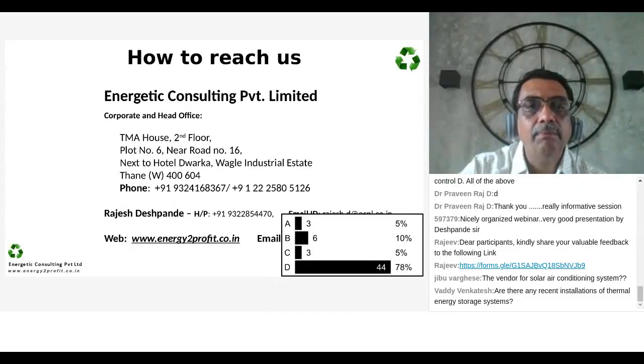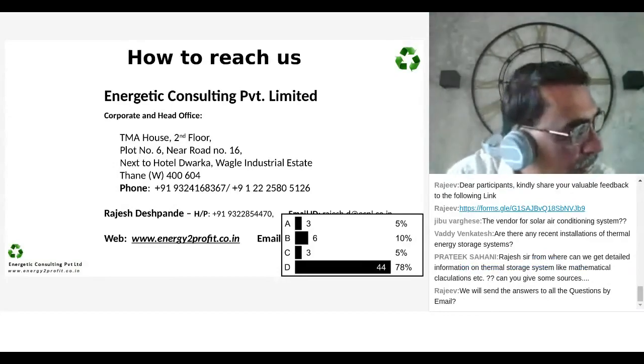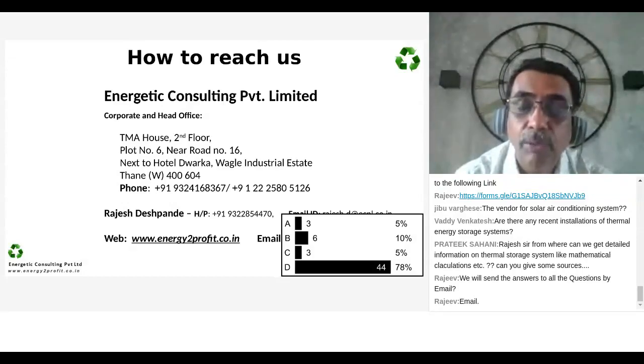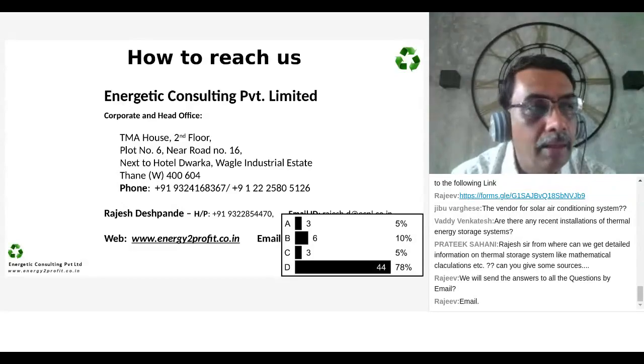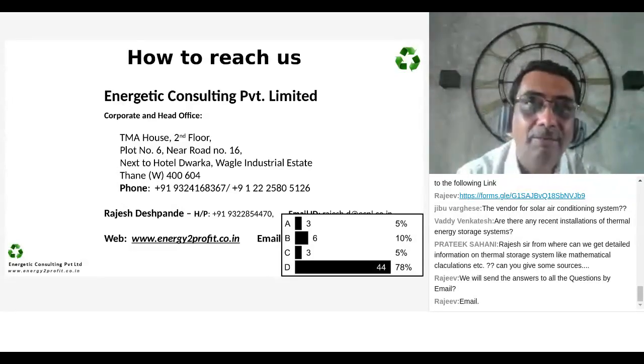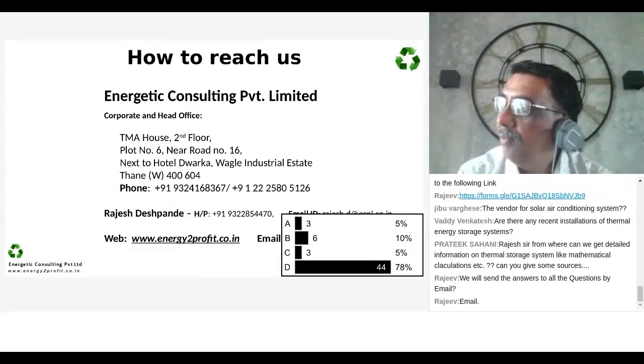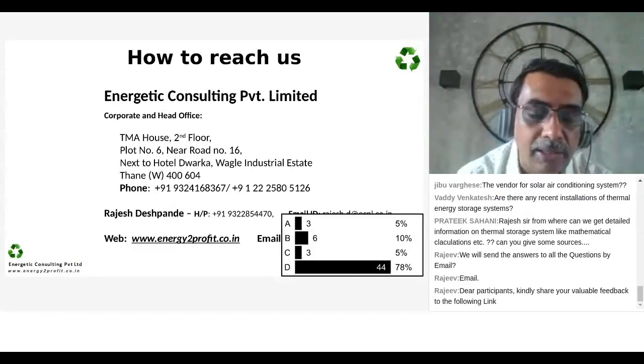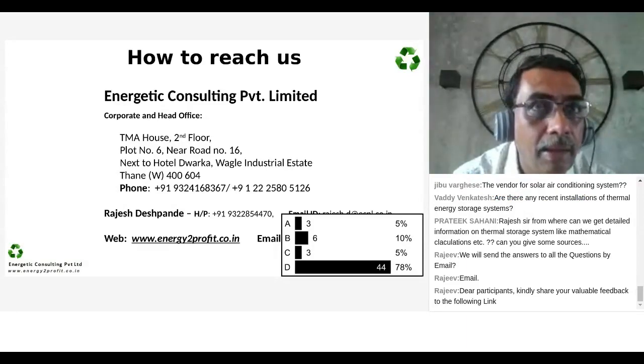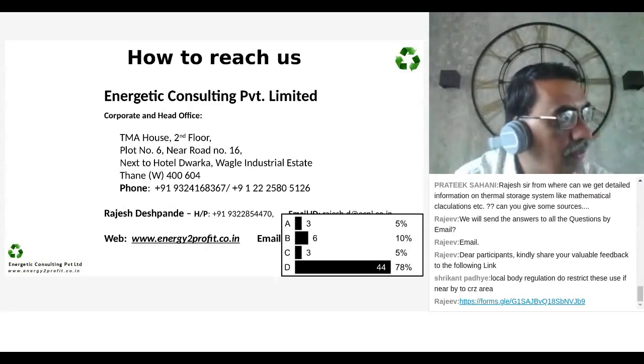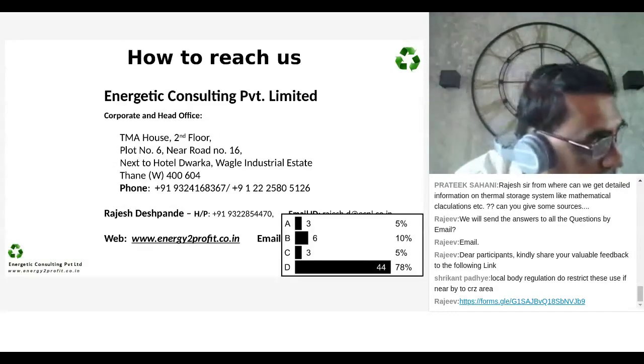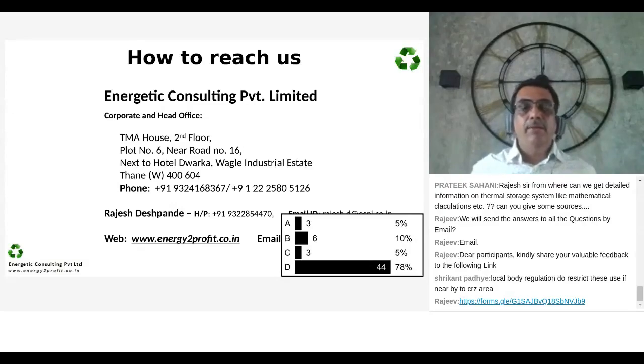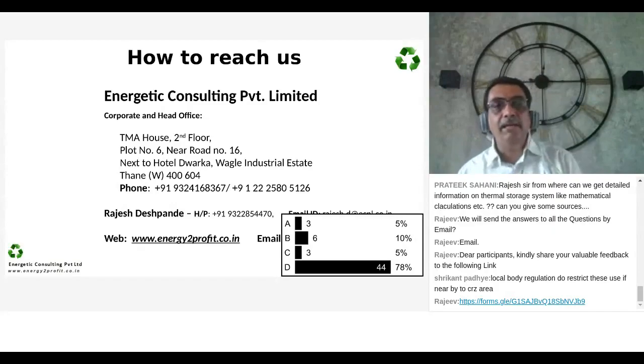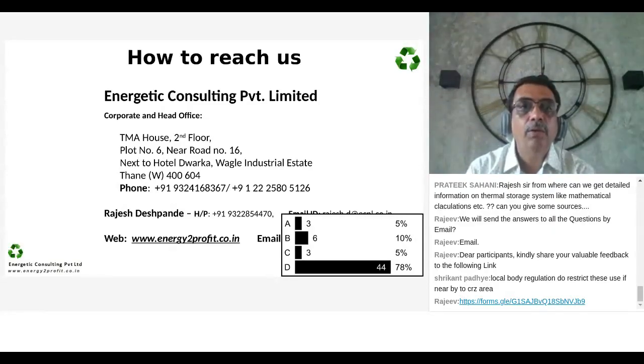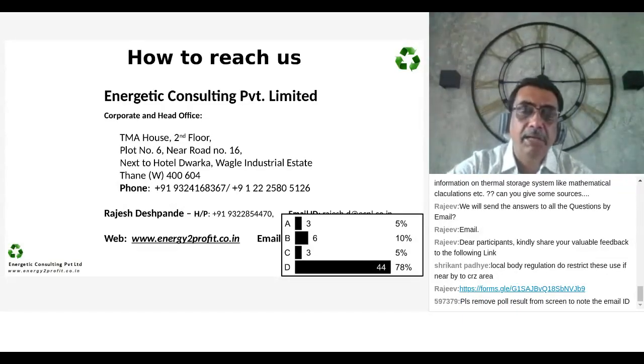The question is, thermal storage system effectively works for this and is not useful for 3-star. I do not really agree with this, because the first one to install was Orchid Hotels. That's a 3-star hotel. Definitely in 3-star or 5-star hotels, we have seen that the demand curve is not exactly bell-shaped. It is more flat. But thermal storage systems can be used for the restaurant and the banquet hall air conditioning systems. You have large banquet halls, large restaurants, eat-out zones, and some shopping malls in the 3-star hotels. Those operate during the daytime. These are the ones where thermal storage becomes very effective, and in fact it is more convenient to integrate it that way. It need not be for the entire 30% load. That I agree.